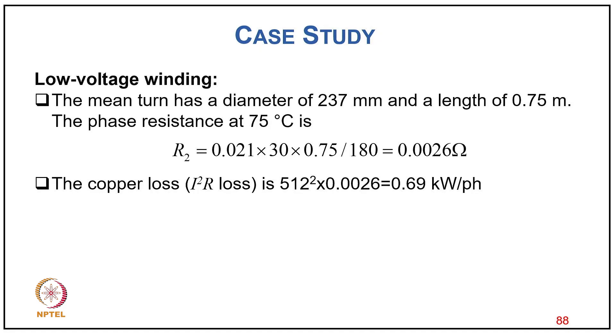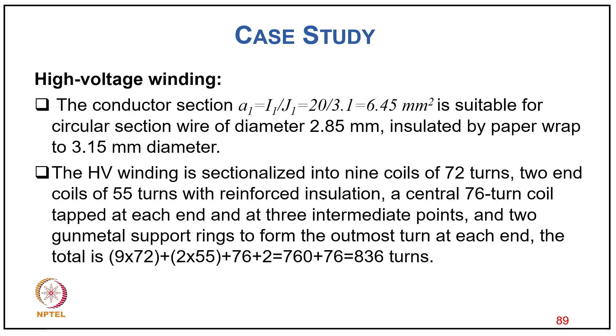The LV winding has mean turn diameter 237 mm and mean turn length 0.75 m. Phase resistance at 75°C: R2 = ρ × 0.75 × 30 / 180 = 0.0026 Ω. Copper loss = I²R = 512² × 0.0026 = 0.69 kW per phase. For the HV winding: conductor area A1 = I1/J1 = 20/3.1 → approximately 6.45 mm², suitable for a circular conductor of 2.85 mm diameter, insulated with paper wrap to 3.15 mm diameter.